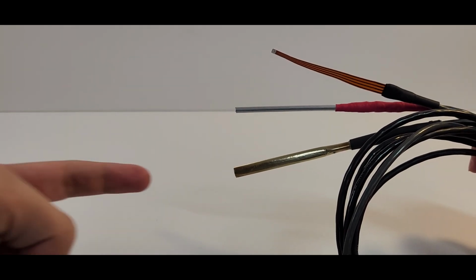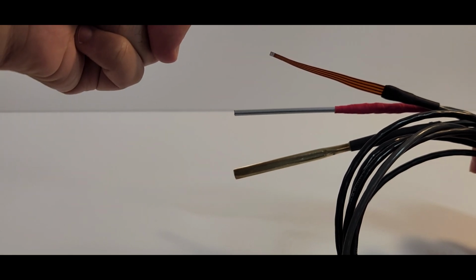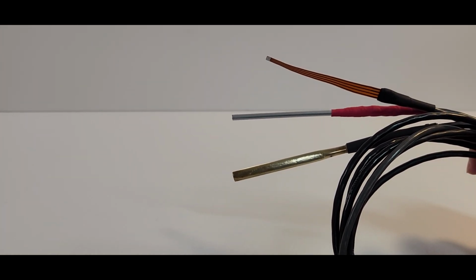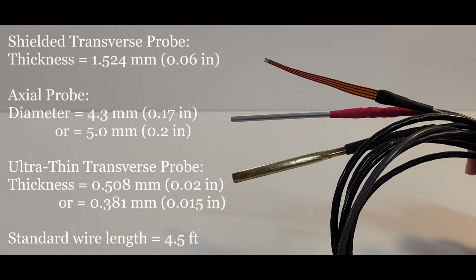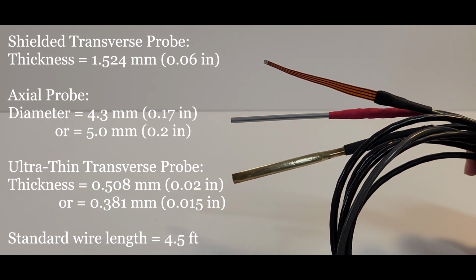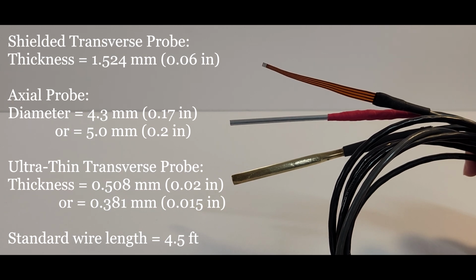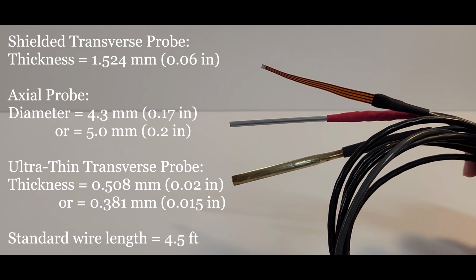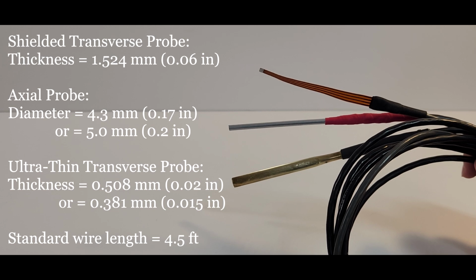Integrity Design offers transverse, axial, and ultra-thin probes that excel in fitting into small gaps in difficult-to-reach locations. The IDR 325 shielded transverse probe has a thickness of 1.524 millimeters. The axial probe has a diameter of 4.3 millimeters and also 5 millimeters. Lastly, the ultra-thin transverse probe has a thickness of either 0.508 millimeters or 0.381 millimeters. The standard wire lengths for all three are 4.5 feet. However, if you would like a different probe or cable, please contact us directly for custom configurations.